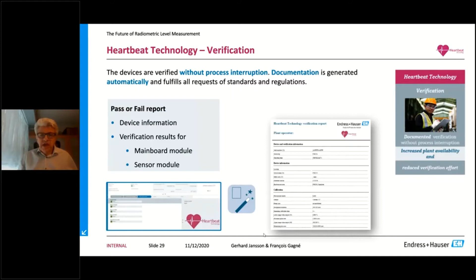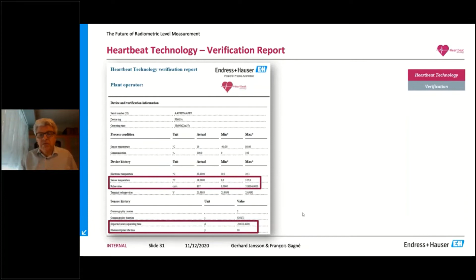In principle, I start this sequence, say please run a verification now, and it will then go through a number of different parameters. It's a pass-fail part to some extent. There can also be those that actually give you values. For instance, sensor temperature allowed between -40 and +80. Right now, in that case, it was 19 degrees C. It will then be on that verification report. These are the actual conditions right now. So there is sensor temperature, pulse values, and so on. Down here at the bottom is the expectation of lifetime for the photomultiplier, how long we can expect the source activity to last. So these are things that can then be used in the monitoring parameters.